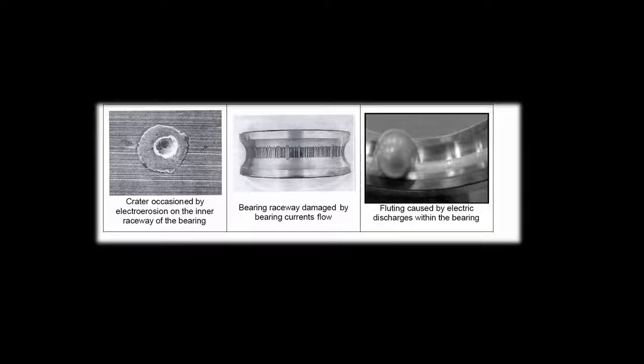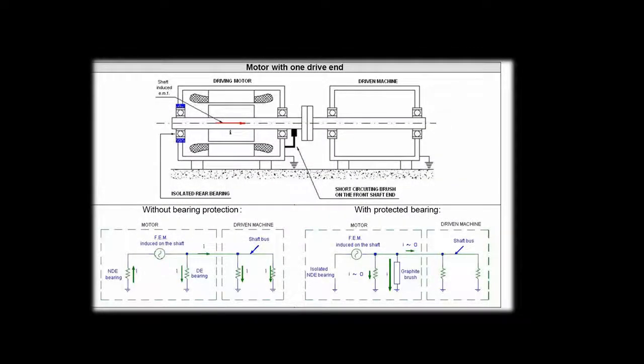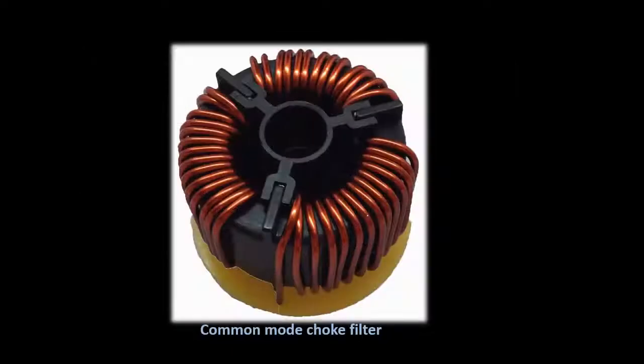A solution to this is to use insulated bearings, and provide an alternative path to earth using a slip ring and brush commutator. Certain filter constructions can also act to dampen out the common mode voltage.